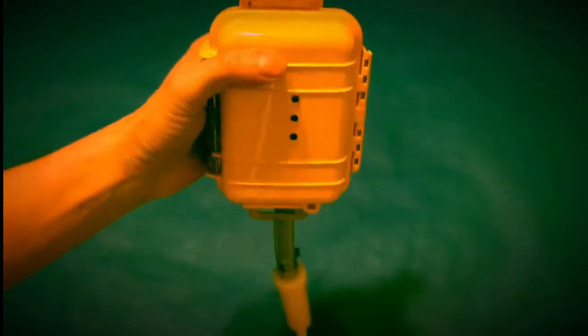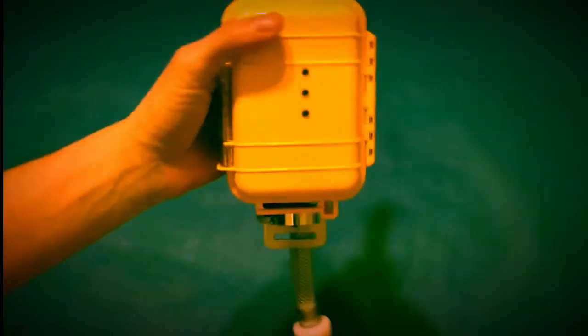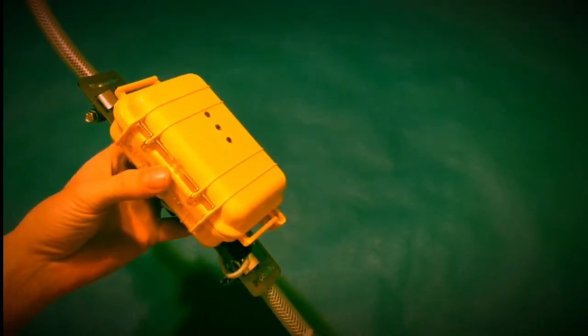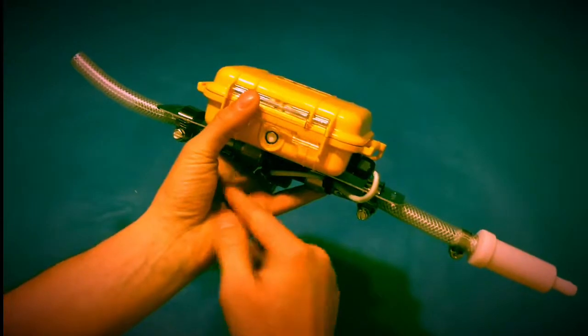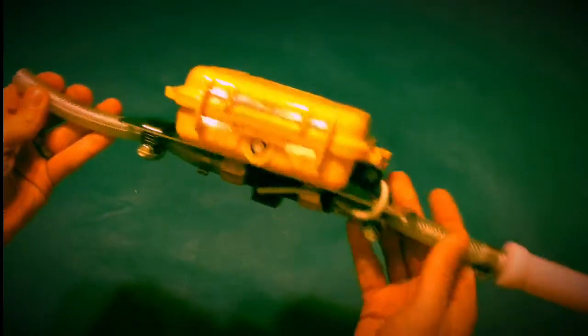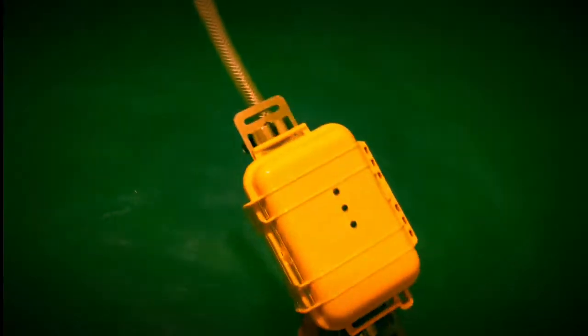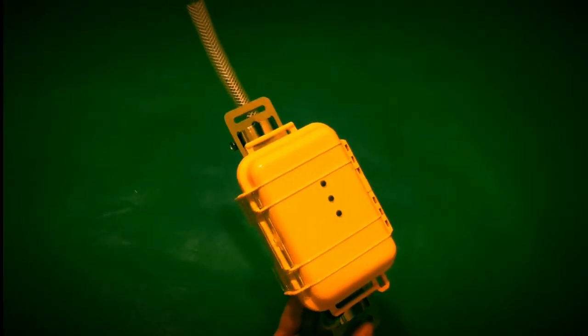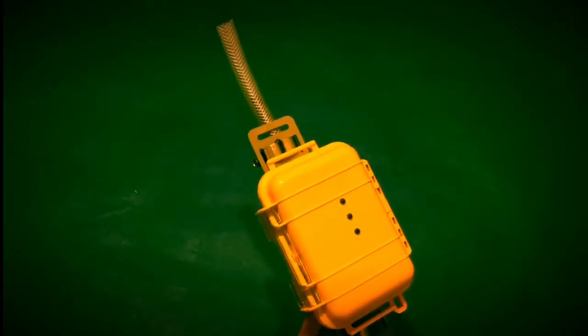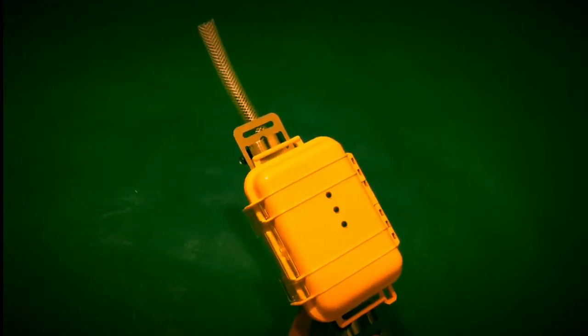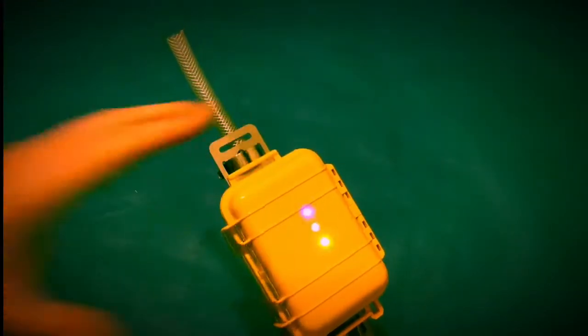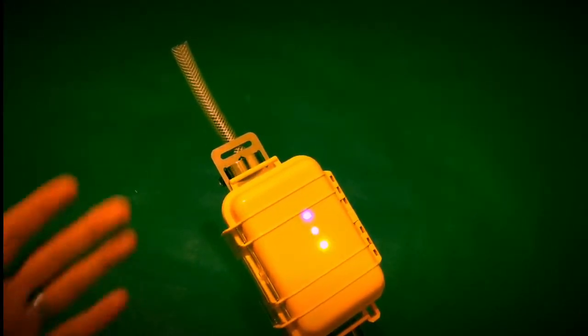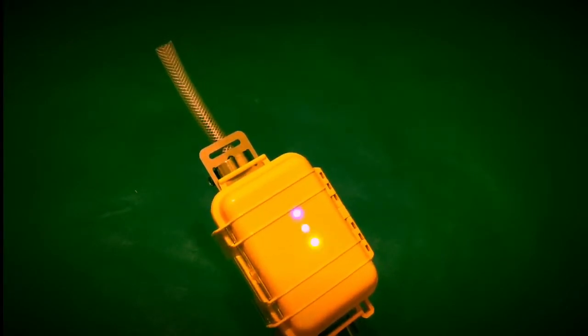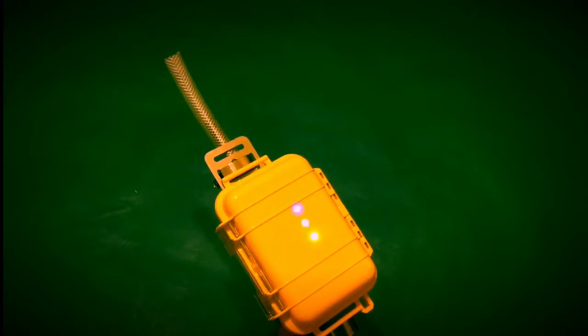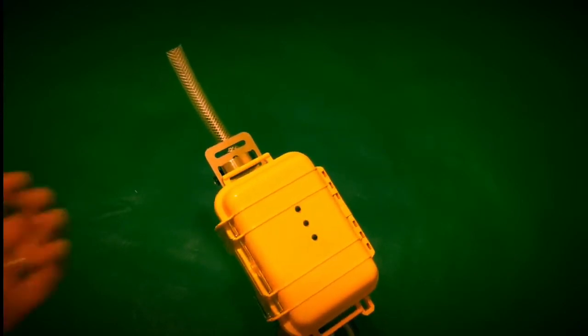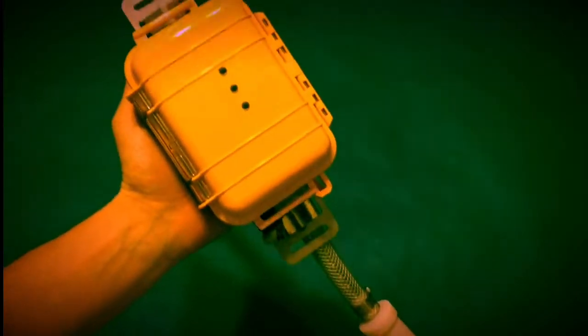What this is going to be doing is that this one is set so that it's recording all the flow that's going through this system. Every 3 seconds it asks, was there any flow in the past 3 seconds? If there was, then it records that. If there was no flow, it doesn't record it. That way, it's not going to fill up the memory card with all the locations you were at but did not flow. That is an option, but it does start to create a lot of data points.